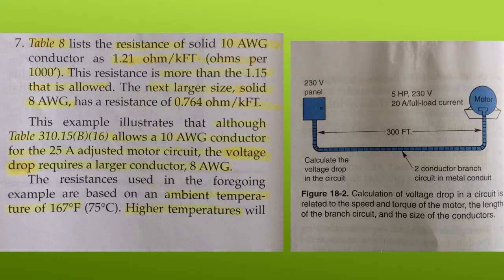Step 7. Use Table 8 of the NEC, which lists the resistance of solid 10 AWG conductor, which is 1.21 ohms per 1,000 foot. This resistance is more than the 1.15 that is allowed. So the next larger size, solid 8 AWG, has a resistance of 0.764 ohms per 1,000 foot. So this example illustrates that although Table 310.15(B)(16) allows a 10 AWG conductor for the 25 amp adjusted motor circuit, the voltage drop requires a larger conductor, which is the 8 AWG.